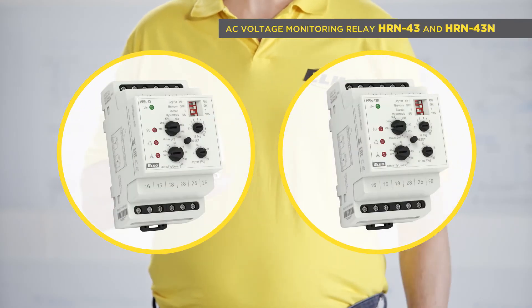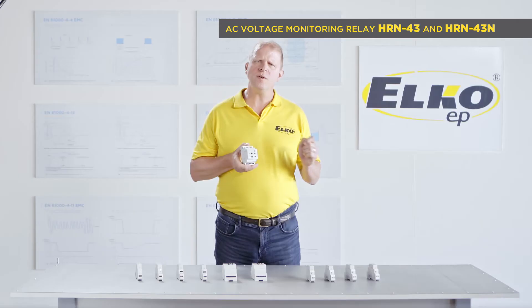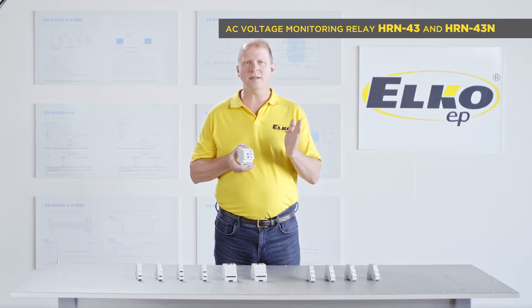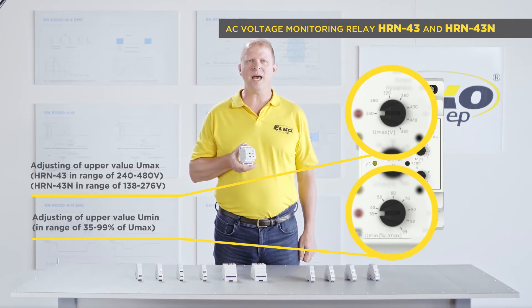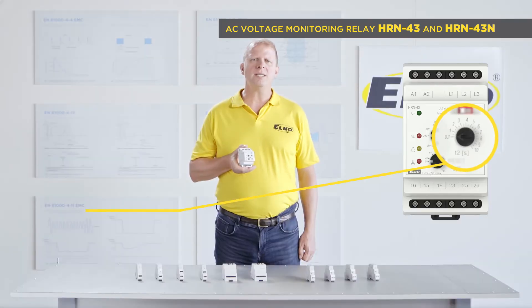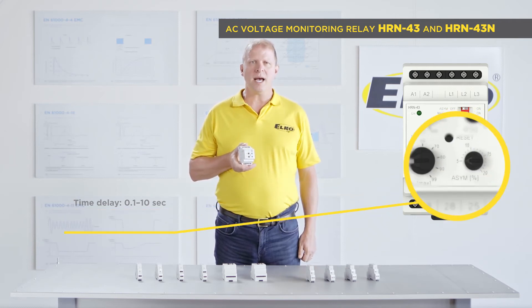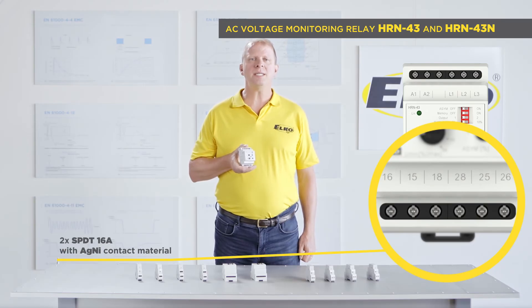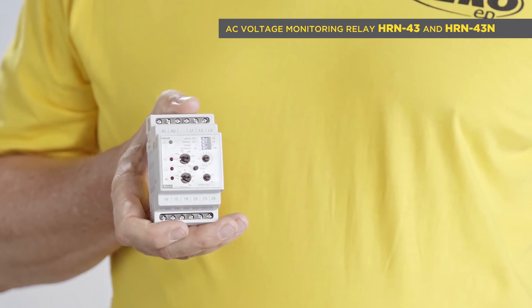HRN 43 is intended for monitoring phase sequence, phase failure, and phase asymmetry. It also controls over voltage in a range of 240 to 480 volts, or 138 to 276 volts in HRN 43N, and under voltage in a range of 35 to 99 percent of the over voltage. It has an adjustable time delay of 0.1 to 10 seconds for eliminating short peaks, and two output relays with an SPDT 16 amp changeover contact. The galvanically separated power supply for monitoring inputs is available in four options: AC/DC 24 volts and AC 110, 230, and 400 volts.